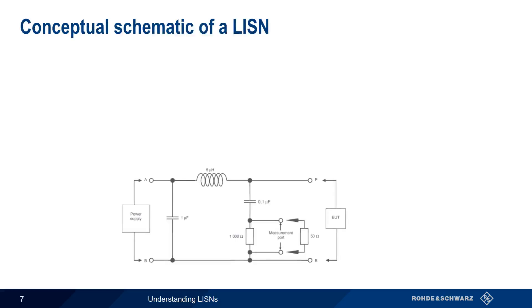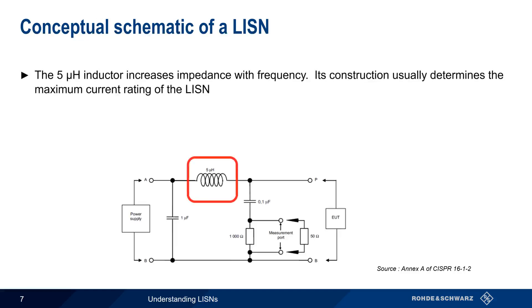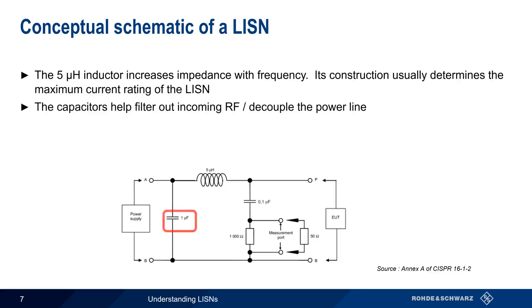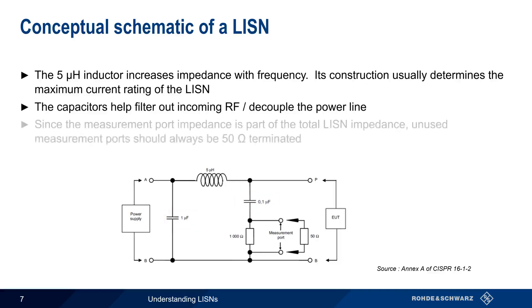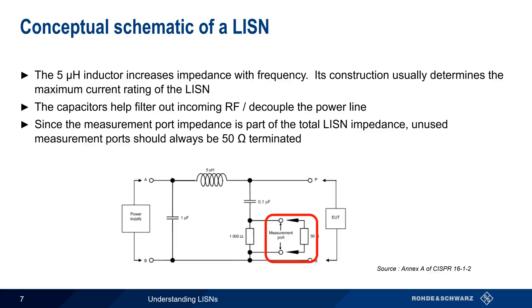Let's look at a conceptual schematic of a LISN, taken from Annex A of CISPR-16-1-2. The 5 µH inductor increases impedance with increasing frequency, and its construction usually determines the maximum current rating of a given LISN. The capacitors help to both filter any incoming RF and decouple the power line. Finally, note that since the measurement port is part of the total LISN impedance, this port should be 50 ohm terminated when not in use.